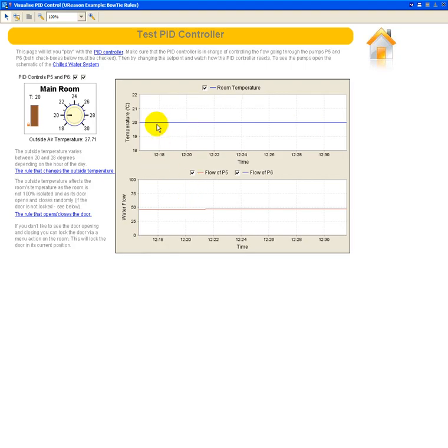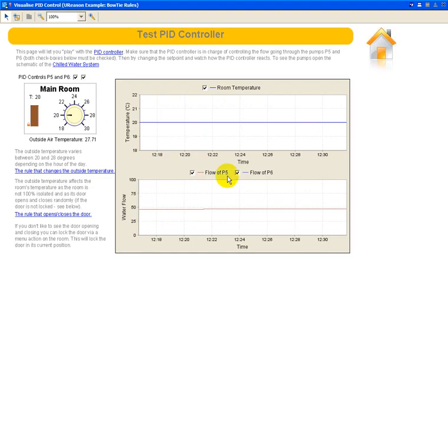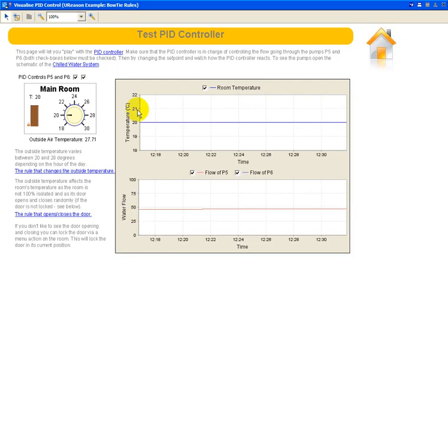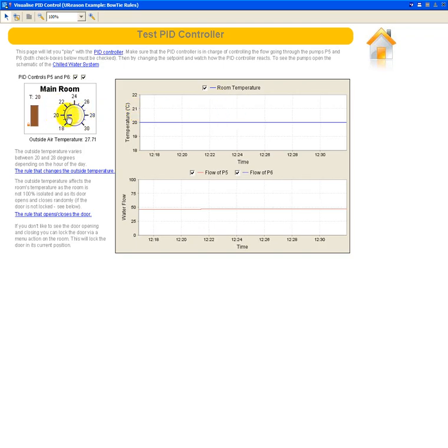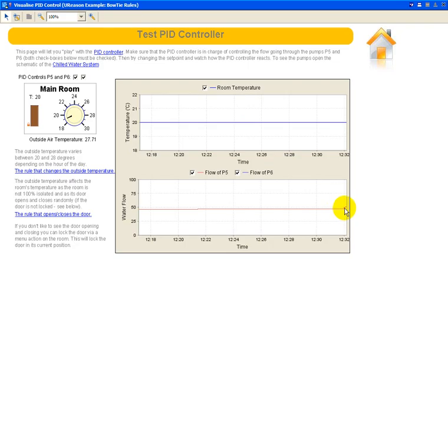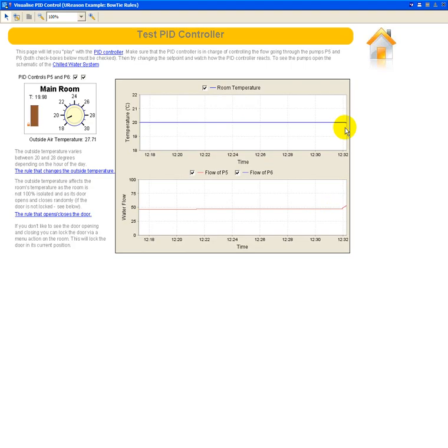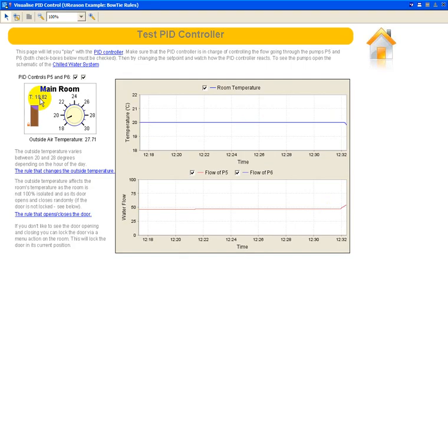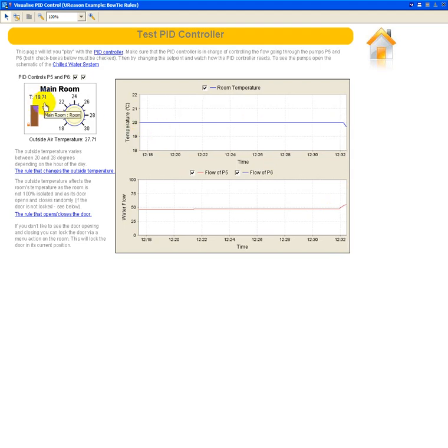To get these 20 degrees there, the PID is actually asking both pumps, P5 and P6, to run at the same flow at almost 50 here. If we change the set point, we'll see the effect on that. So if I ask a different temperature, I've asked the system to reduce the temperature inside the room. The PID should react and slowly ask the pump to push a little bit more flow so that the temperature here can decrease from 20 to 19 degrees. So we'll see here slowly the temperature of the room, leaving now the 20 degrees and going to 19 degrees. Hopefully it should now stabilize around that value in a few minutes.